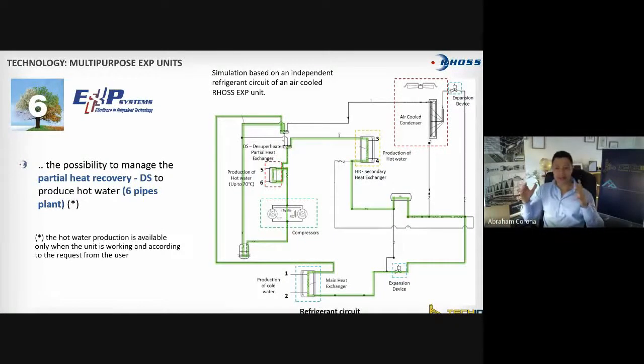So now what is a 6-pipe system? I think it's very clear that we're not talking about a water-cooled unit, all right? So now a 6-pipe system is what we call an extra plus. We are able to get another heat exchanger. Before, we had the main heat exchanger that we call mainly the evaporator, and the secondary heat exchanger that works like a total heat recovery of the unit, and we can install what we call the desuperheater or partial heat recovery straight out of the compressor. That gives you the possibility to produce water up to 70 degrees. You're going to tell me, Aaron, before you were telling me we'll go up to 55, and now you're telling me we can go up to 70. Yeah, the truth is, as soon as you are at the compressor, the gas temperatures there are really close to or well above 100 degrees. That is the reason we can get 70 degrees there, all right?